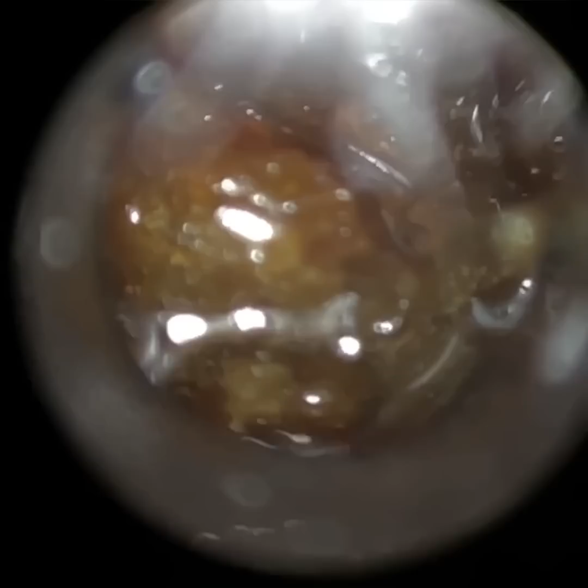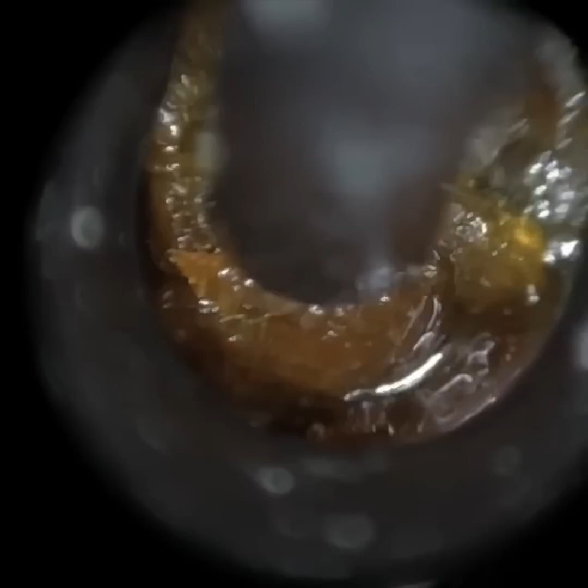So here comes the WAXscope. The WAXscope, in terms of an endoscope, is much easier to hold, and it's got a speculum attachment, as you can see. In comparison to head loupes, the magnification's on a different league. In fact, the magnification of the WAXscope you can put on par with an ENT microscope. Unlike an ENT microscope, the WAXscope is portable, it's significantly cheaper. In terms of constant readjustments, they're so much easier to make. It's just a swipe on the screen. You adjust the focus on the screen. We've even got a double tap autofocus. So we've overcome that. If the patient moves slightly, it's not an issue because the speculum is already there, and you've already got it fully inserted. You're just going to make adjustments on the screen.